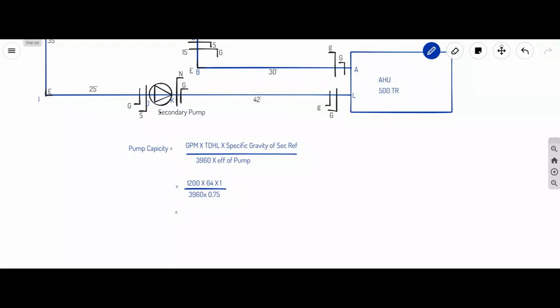So 1200 into 64 into specific gravity, divided by 3960, divided by 0.75. That is 25 HP. So this is how we find the capacity of the pump. Clear? Yes, sir. Make a note.